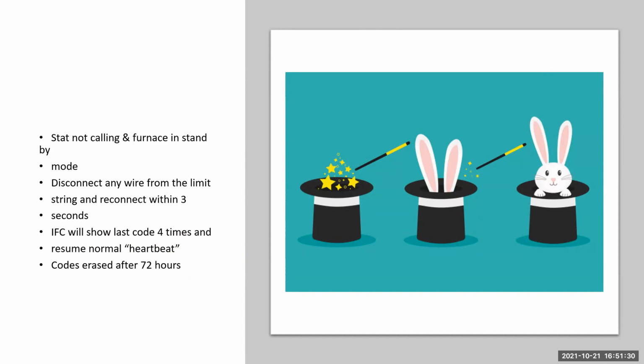fault codes here. If you get to a system and you don't have a current fault, you can remove any wire off the limit circuit, your red wires. Pull it off, put it right back on. Your code will come back and it'll flash 4 times. And then you're going to resume your normal heartbeat. If you're past 72 hours of your last fault, you will not be able to pull it back off. Most of our newer stuff is running off UI, so you're going to find your faults there. But if you don't have a UI, you can pull it off the board as long as you're there within 72 hours of its last event.